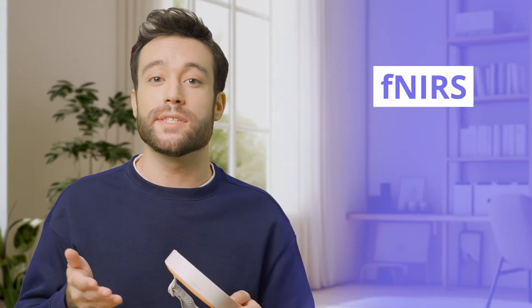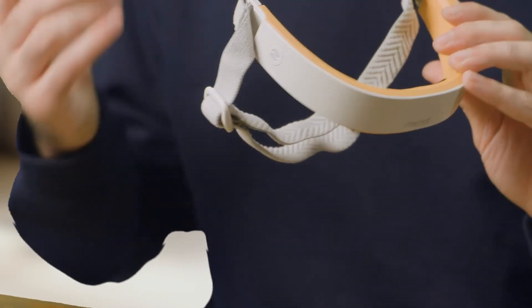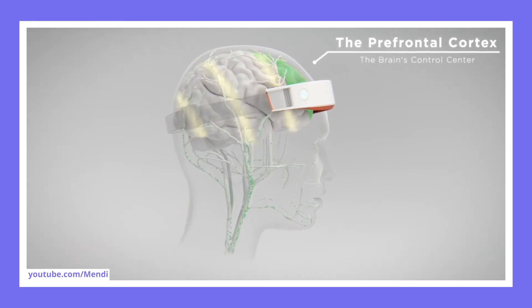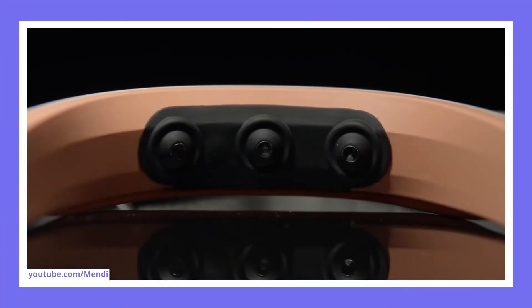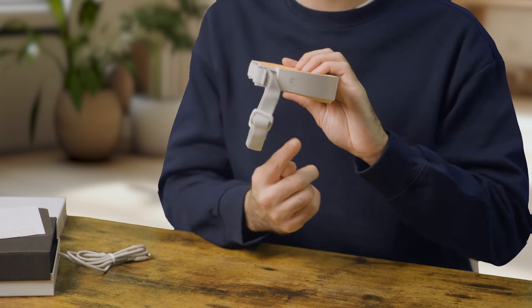Now let's delve into the technological heart of Mendi. The device uses fNIRS technology, a non-invasive way to measure brain activity. It utilizes red light and near-infrared light to measure blood flow and oxygenation in the prefrontal cortex. The central emitter sends out red light at 660 nanometers and near-infrared at 800 nanometer wavelengths that bounce back to the sensors, allowing the device to track your brain function. Two additional sensors are placed five centimeters left and right from the central emitter, plus a scalp sensor one centimeter to the right of the central emitter for more precise readings.